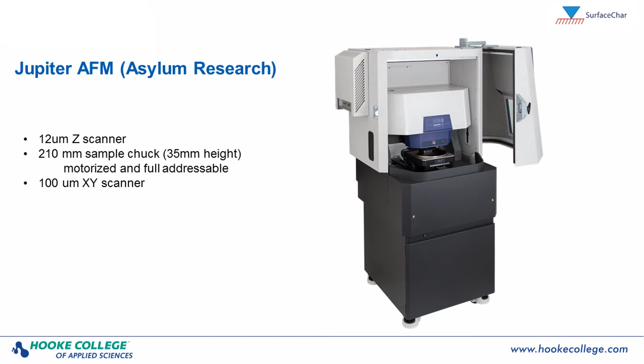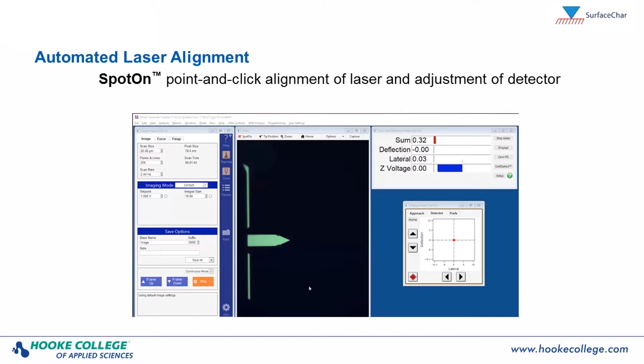One is automated laser alignment, a step in running AFMs that a lot of users struggle with. They've integrated point and click alignment of the laser onto this cantilever here. It's similar to the point and click alignment they have on their small sample instruments, but it makes laser alignment fairly trivial, so that's good. Another feature they've integrated into this large sample instrument is how we drive the cantilever. Driving the cantilever means that we shake it so that it oscillates, typically at a resonance frequency, so that we can image in modes called tapping mode, for example.